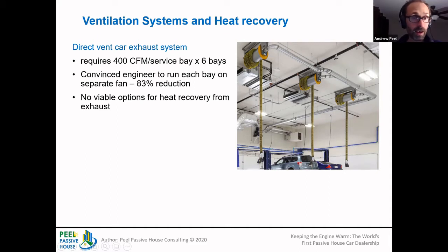We did also look at heat recovery on this exhaust for the makeup air. We looked at all sorts of stuff: a heat recovery unit like an HRV, a tube in tube, a heat pipe. And in the end, no manufacturer would actually warranty their equipment for dealing with car exhaust. So we had no viable heat recovery.